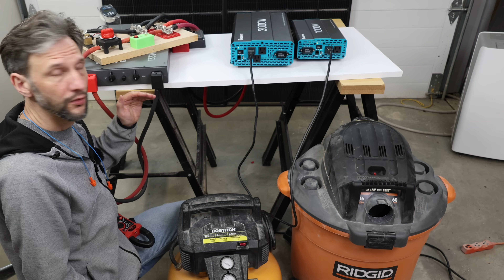I'm going to hook this up to an 8,000 watt 48 volt inverter and we'll see what we can do with it. We'll only have 200 amps available when you put these in series. Even though I'm going to put 4 of them in series, you're limited to the minimum amperage of one battery. When we put 4 of these in parallel for 12 volts, we get 800 amps, but you'll see at 48 volts we don't need all that current, which means smaller cables, a lot less stress on the joints. So let's check that one out.